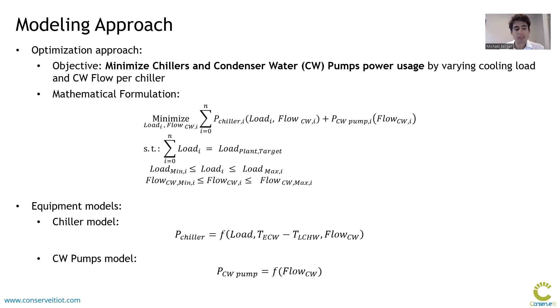You can see the models of each component. The chiller model uses as variables the cooling load, entering condenser water temperature, leaving chiller temperature, and condenser flow. The condenser pump model uses the condenser flow as the input variable. Note that this optimization can be extended to find the optimum number of chillers as well, by repeating the optimization several times with different numbers of chillers and finding the case that further minimizes the power usage of the plant.